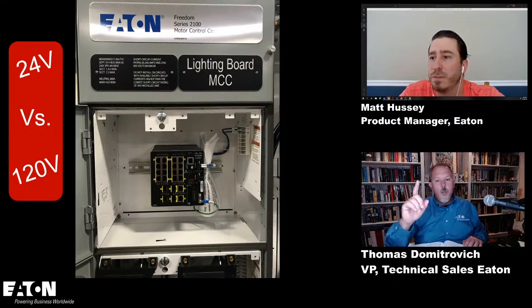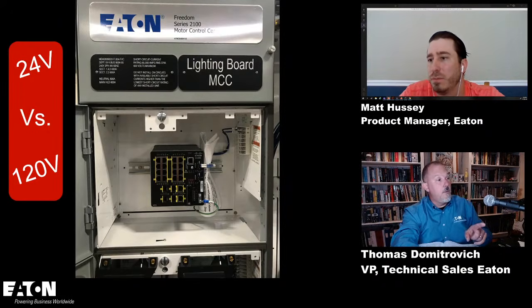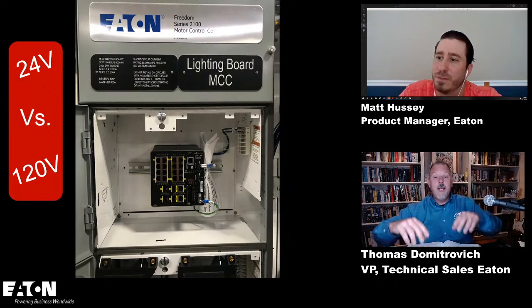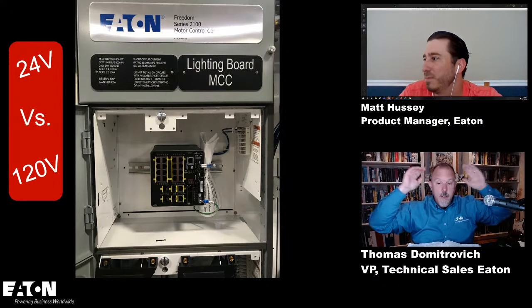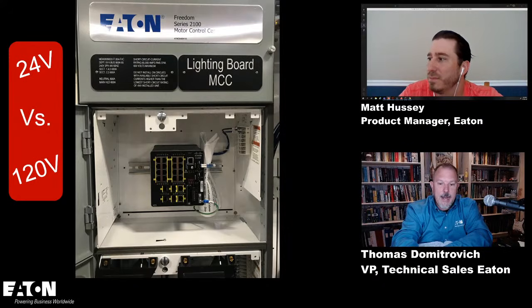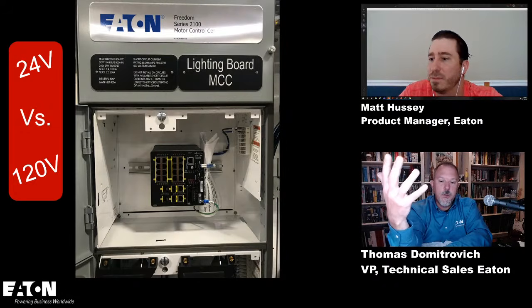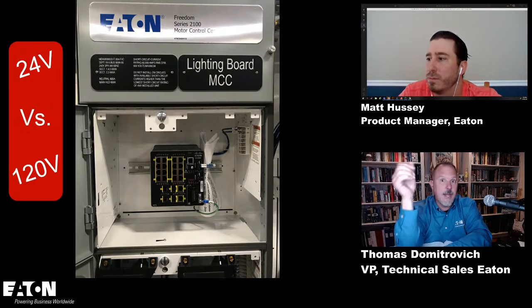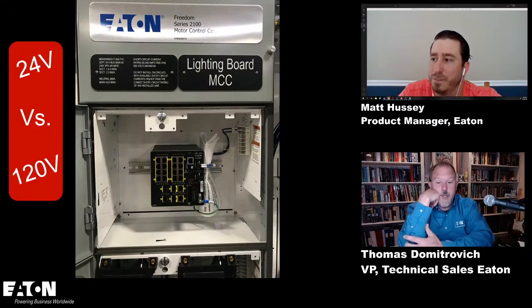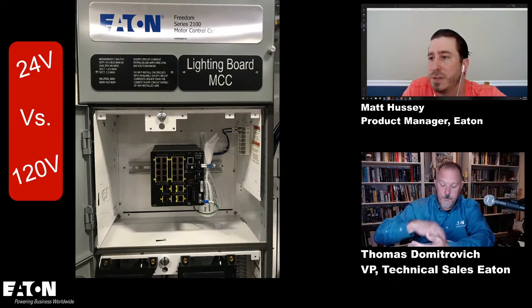But wait a second. So when I take this bucket out, let's say I bought one from you. Let's say I called Matt Hussey, and Matt said, I got you covered, Tom, I'm going to give you a bucket. It's going to have a breaker in there, and it's got the three stabs on the back that go right onto the bus. When I pull this bucket out, are there receptacles behind that bucket ready for the new bucket that I could just plug in, or is it just bare copper bus? No, there's basically bus connections that should be there, and then the new bucket's going to have stab connections to connect onto that bus.